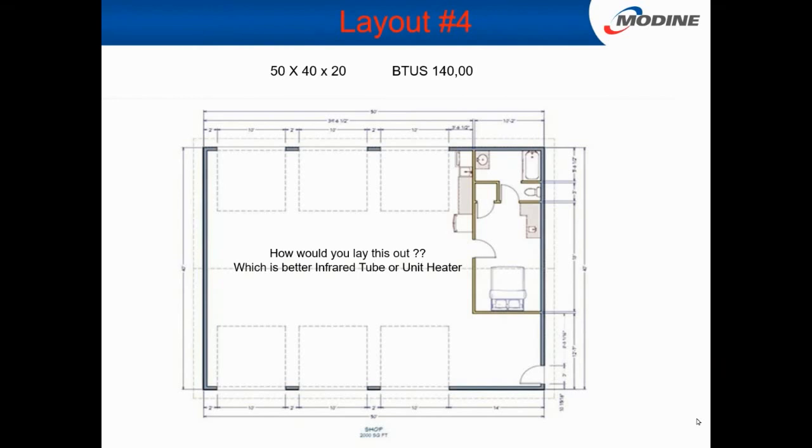At 140,000 though, you're probably going to have to put a 175 in there. And because of the length here, that's 50 minus 12, so 38. You take that times 1.5 to get how long a tube you need. 38 times 1.5 is 57. But we've only got 48 right there, so 47 is not much of a throw. In that particular application, we might have to go with maybe a 40-foot U-tube and use that. That would work good. There are all kinds of options you can do with this.